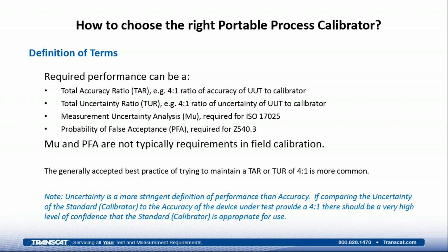Measurement uncertainty analysis and probability of false acceptance are typically not required in field calibration. So we revert to the generally accepted best practice of trying to maintain an accuracy ratio or uncertainty ratio, probably more commonly an accuracy ratio, of 4-to-1, which is much more common. Just to note, and hopefully tie this all together, uncertainty is a much more stringent definition of performance than accuracy. It takes into account, in addition to what's defined in accuracy, a lot of other potential error sources.